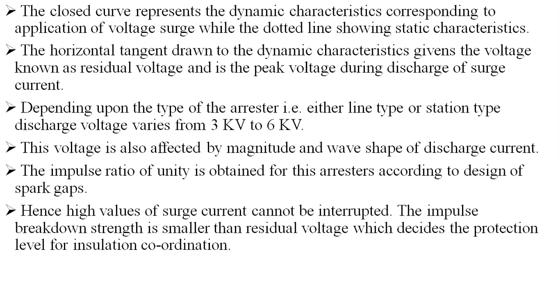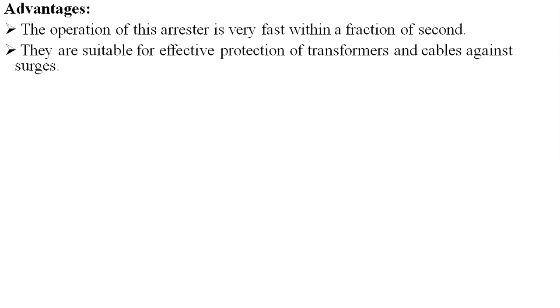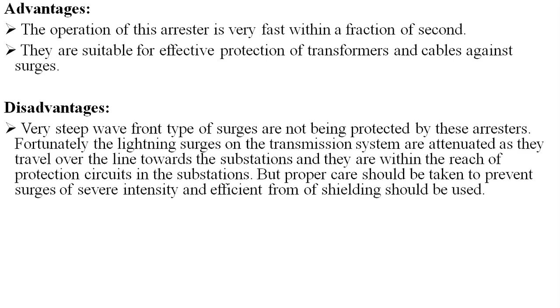Coming to the advantages, the operation of this arrestor is very fast, within a fraction of a second, and they are suitable for effective protection of transformers and cables against surges. And what are the disadvantages? Very steep wave front surges are not protected by these arrestors. Fortunately, the lightning surges on the transmission system are attenuated as they travel over the line towards the substations, and they are within the reach of the protection circuits in the substations. But proper care should be taken to prevent surges of severe intensity, and an efficient form of shielding should be used.